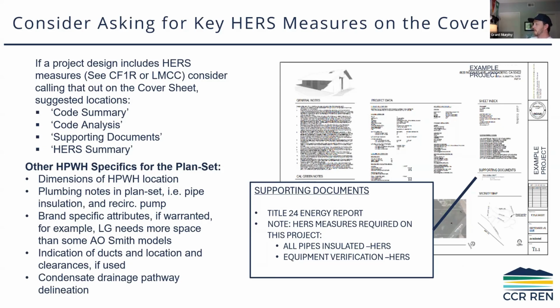Last I checked, when you dig deep into the spec sheets, many of these heat pump water heaters, when the intake ambient temp is below 40 degrees, a lot of them kick into electric resistance mode. And I know that number is hopefully coming down at some rate with new models coming out. But if it's below 40 for any certain duration of time, that unit is going to operate inefficiently. Yeah, we should be designing for these things to be inside conditioned space or have intakes where we can control that intake temperature. So for Pam's climate where she's at, the way Jennifer said it, they should be inside. You should not be designing for these things to be hanging out in snow climate.